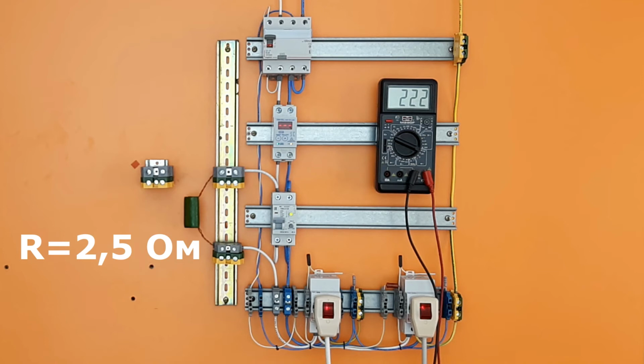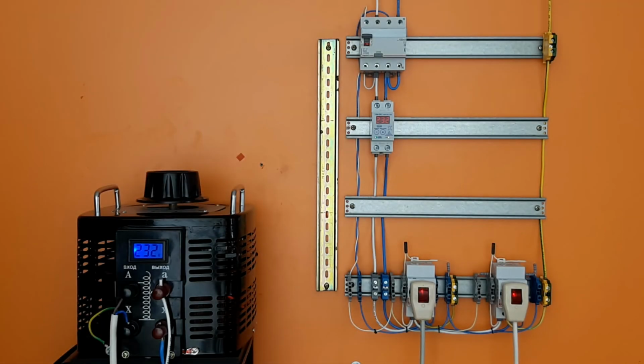The next experiment will repeat the simulation of the situation with an increase in the transient resistance. Put a powerful 2.5 ohm resistor in the gap of the phase conductor. The tester shows the voltage on the load. In other words, it takes into account the drop on the resistor. We change the load stepwise. We see that at a current of 2.4 amps, the voltage has dropped by 10 volts and the protection is not yet triggered. Shutdown is performed at a current of about 6 amperes, just at the time when losses on the resistor could lead to heat and fire. We prevented this, and the AFDD is inactive.